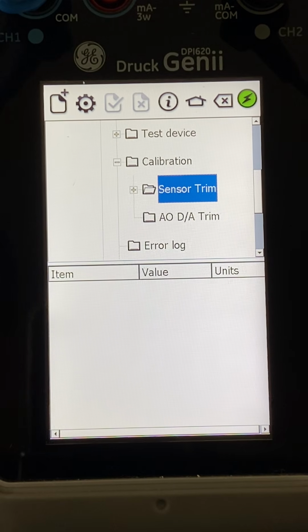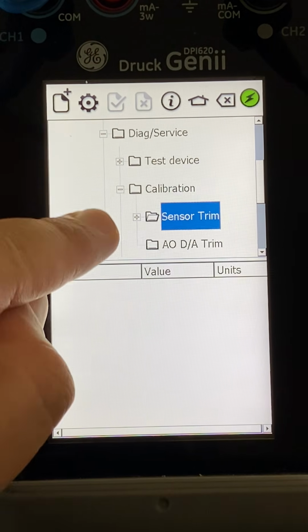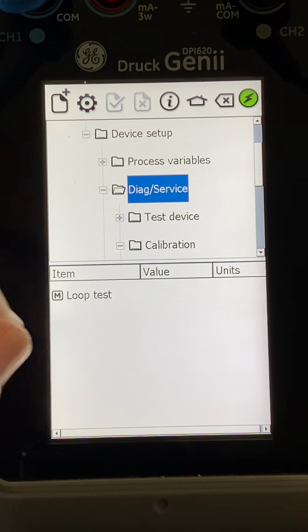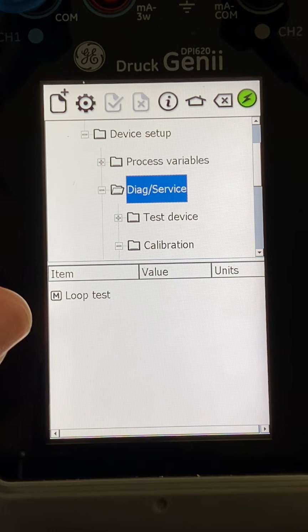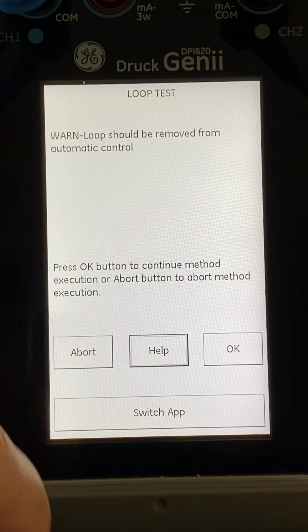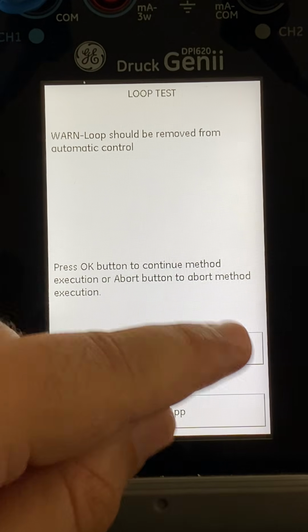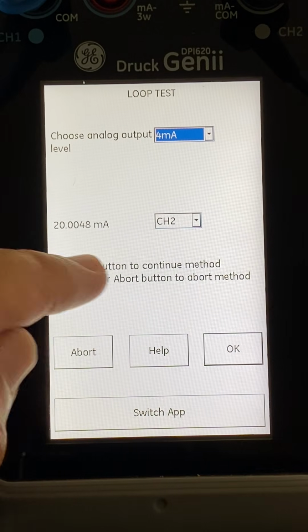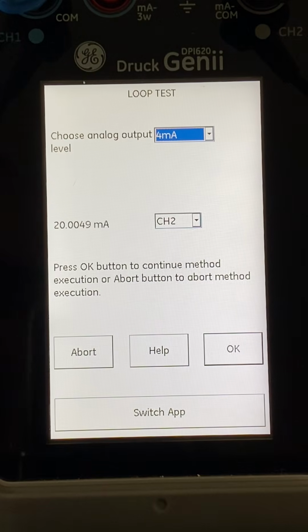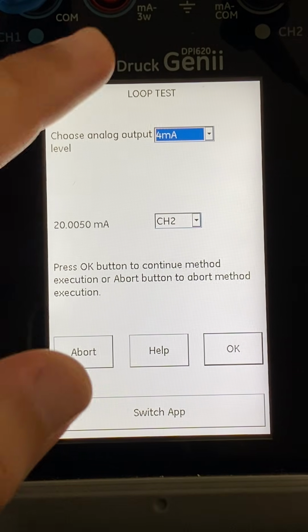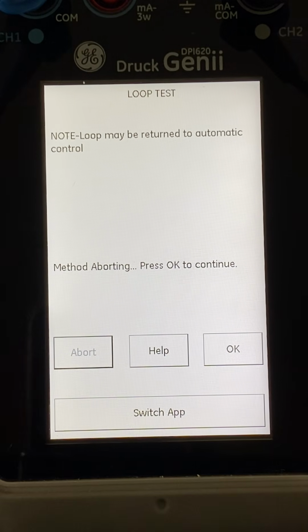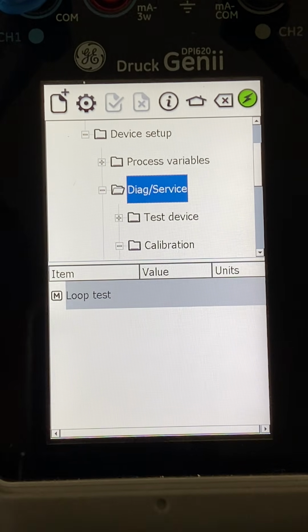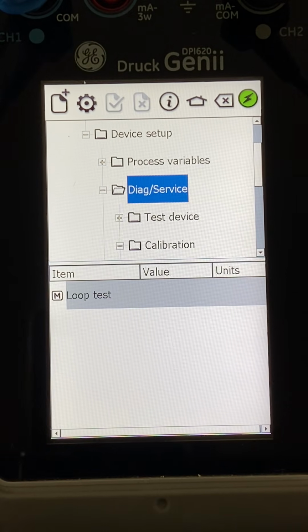Okay, let's see how we can, for example, do a loop test. So here, coming back to diagnostics and services, here is the loop test. If the device is already installed and you want to test the loop, you simply press here and it will perform the 4 milliampere and the 20 milliampere. And this will be injected from channel 2, which means it is also a calibrated signal. So I'll abort that because I'm not connected to a network now. Okay, aborted. Good. Then these are the basic HART functions people are considering.